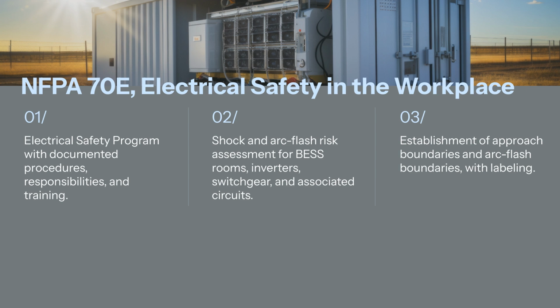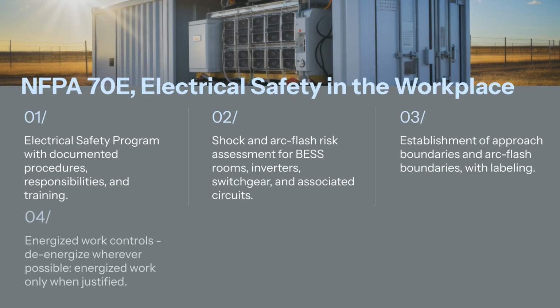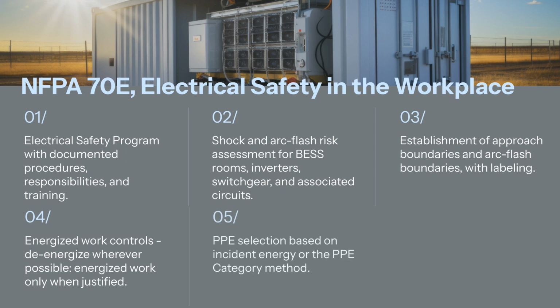Establishment of approach boundaries and arc flash boundaries with labeling. Energized work controls: de-energize wherever possible, and energized work only when justified and authorized. PPE selection based on incident energy, or the PPE category method, and use of properly rated test equipment and insulated tools. OSHA frequently cites NFPA 70E as the primary consensus standard for electrical safety and utilization systems, making 70E aligned programs highly influential in enforcement.